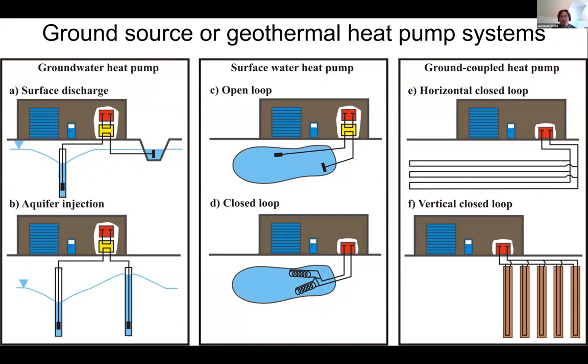Actually, there are different types of geothermal heat pump systems. The groundwater one, on one hand, is a heat pump system where we use the groundwater directly for heating and cooling buildings, and the ground coupled, which are closed loop systems. So it's pipe that is buried in the ground, either horizontally or vertically into boreholes, and which provides the exchange with the ground for efficient heating and cooling.